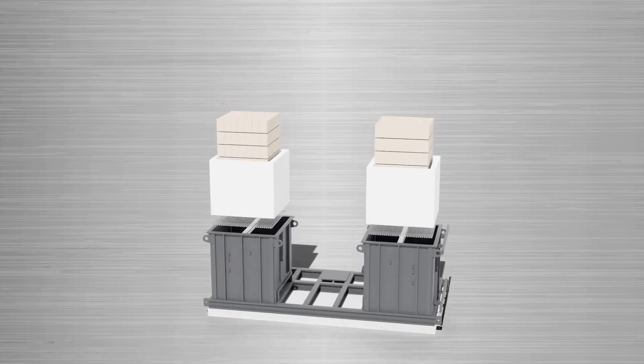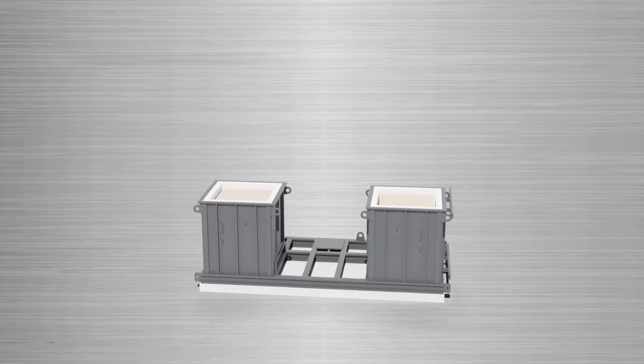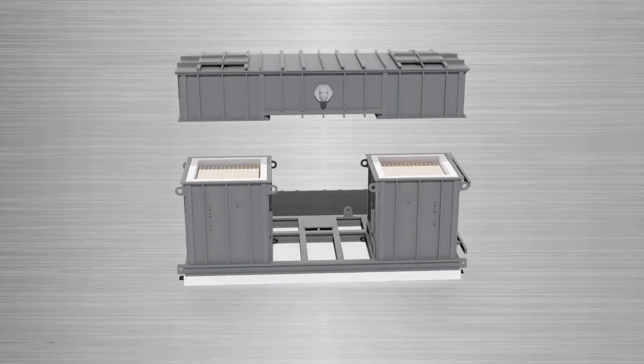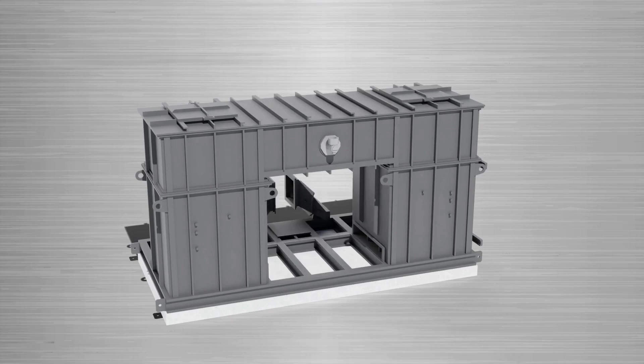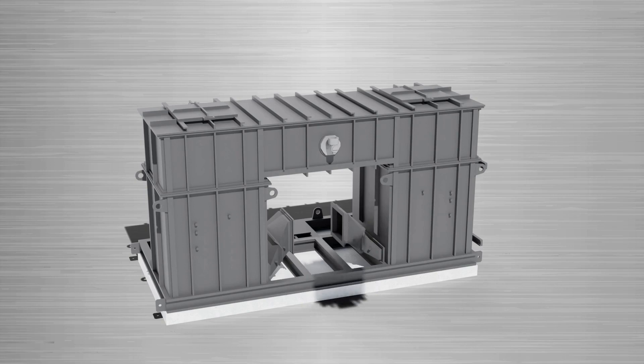Despite internal temperatures that may exceed 1800 degrees Fahrenheit, the oxidation chamber connects the two heat recovery chambers and houses the burner. The heart of the RTO is the QS indexing valve. This specialized valve reverses flow direction in the oxidizer to recover energy from the ceramic media.